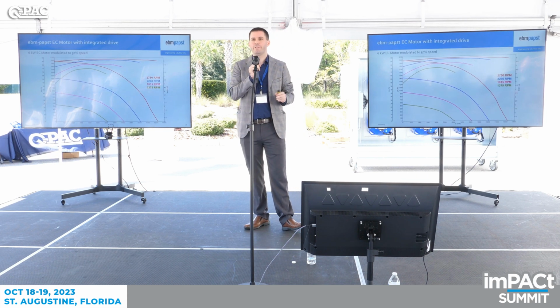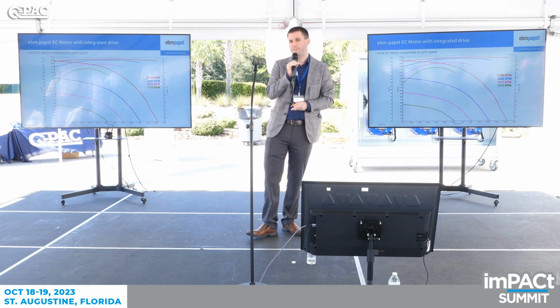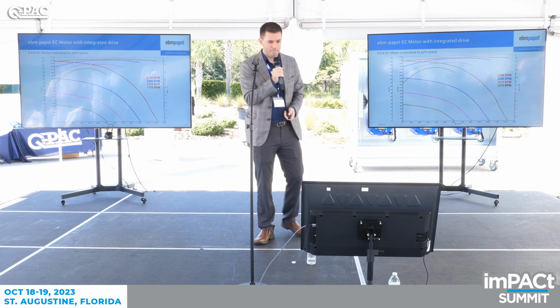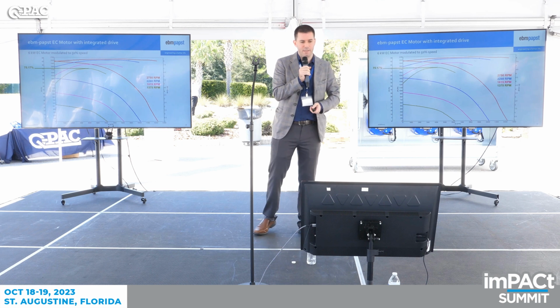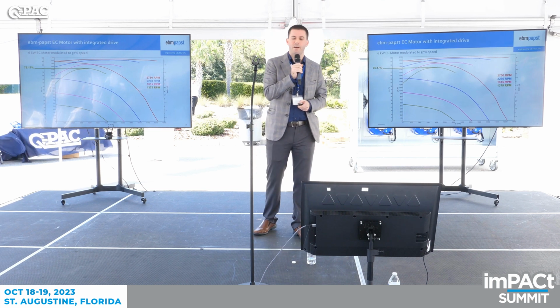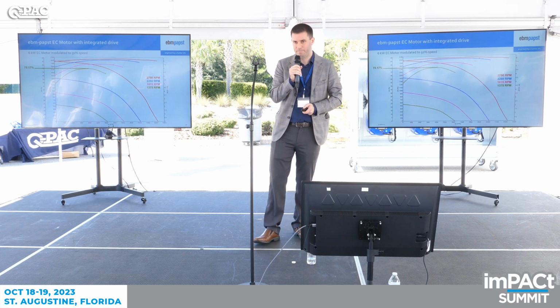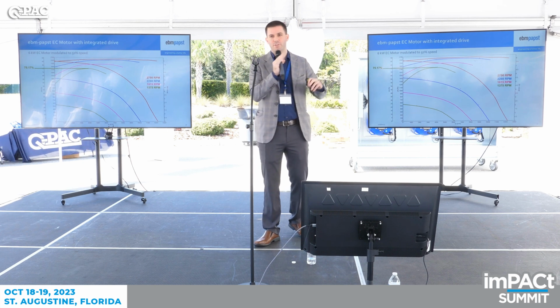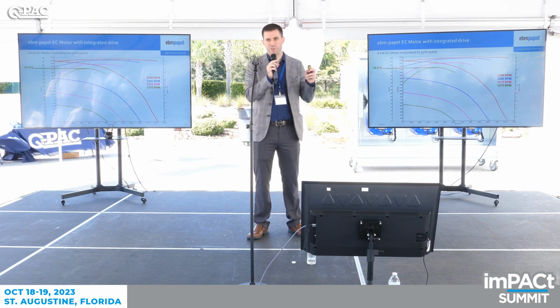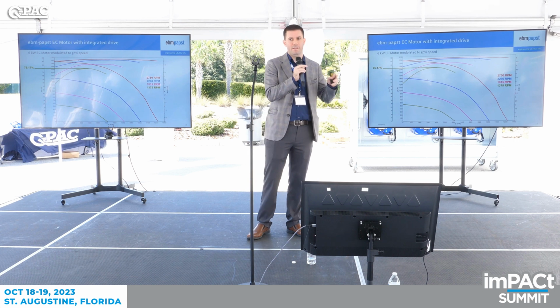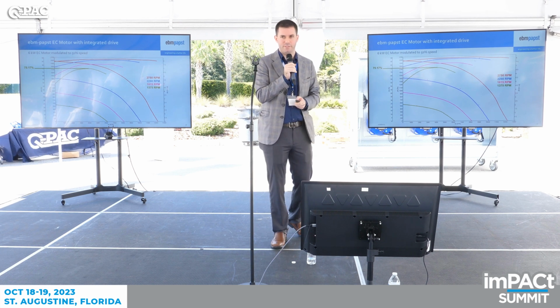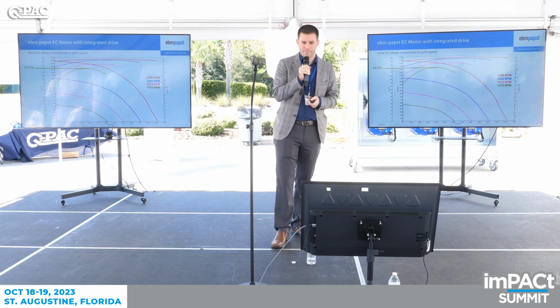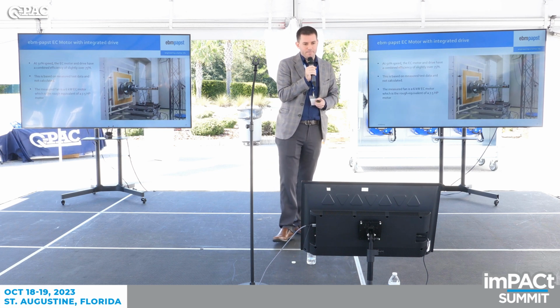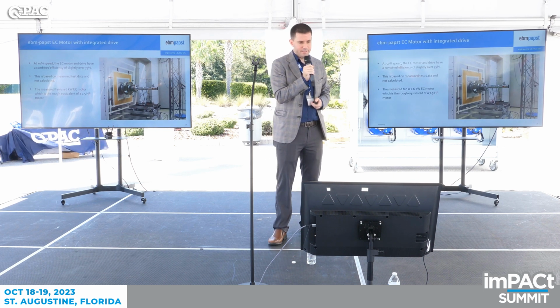So this is some measured data that we did on an airflow chamber of our fan going down to 50% speed. What we found at 50% speed, our motor was still 75.17% efficient. This included the wheel on it. This was the total efficiency, but it was just the motor drive efficiency, not the wheel included. So 75.17% for the motor and drive. This is at 50% speed, based on actual measured test data.